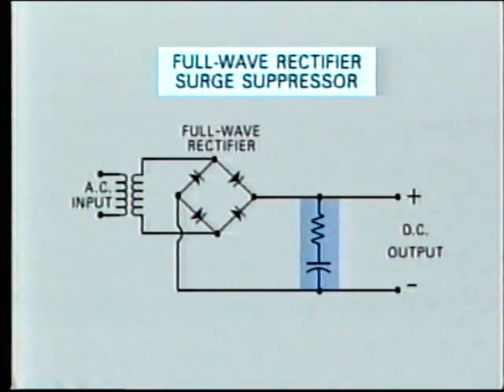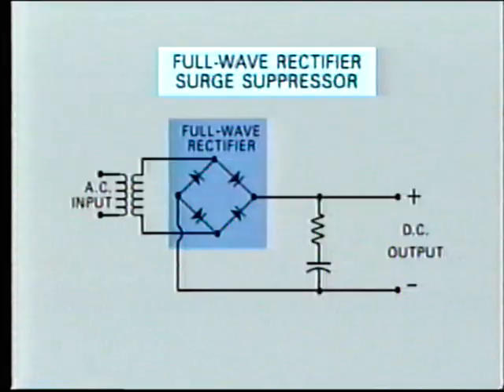Typically, the diverter consists of a capacitance connected across the relay terminals, plus a resistor or inductor in series. This is an example of a surge suppressor for a full wave rectifier. Inside the relay itself, non-linear resistors, such as MOVs, are connected across contacts, and any inductive coils which are in series with the contacts. As you know, the metal oxide varistor offers high resistance at low voltage, but breaks down to low resistance when the voltage rises above a predetermined limit.